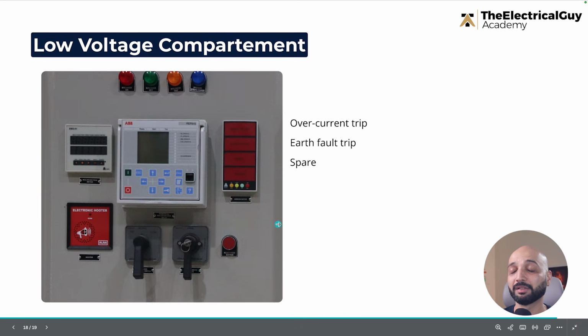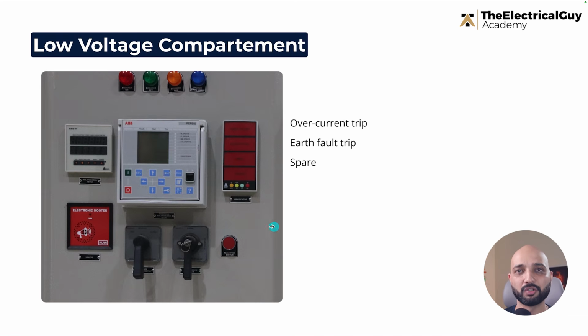And the second switch is the TNC switch, trip, neutral and close. Right, so you can choose whether you want to trip the breaker, or you want to keep it as it is, or you want to close. Where you will turn it, the breaker will operate in that way. And then you also have a reset push button. So this is kind of a master reset. So if there are some faults or maybe annunciators and everything is giving some indication, you can just press that and everything will be reset.